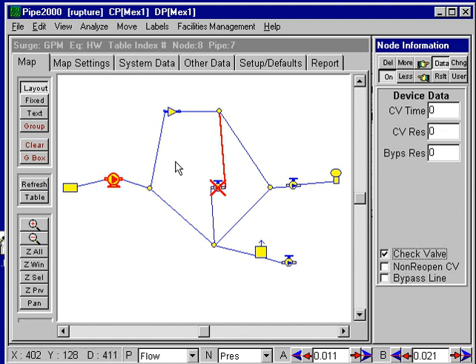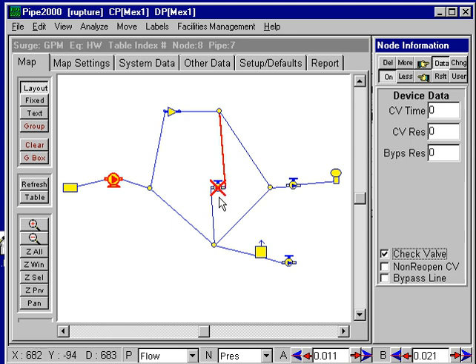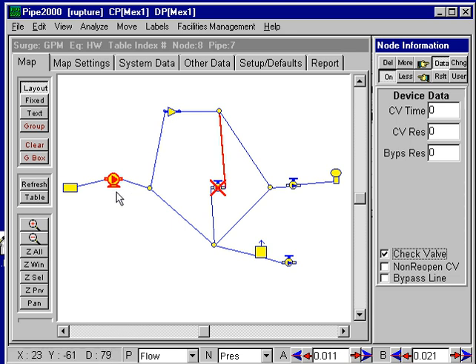So these are four items that we have to deal with differently in Surge 2000. If there's a check valve in the line, put an active valve in and specify that it has a check valve. If there's a closed line, show an active valve at the shut location and close it. For regulators, they're treated as constant resistance devices. And pumps don't automatically have check valves — if we want one, we select that pump and put in the check valve information.